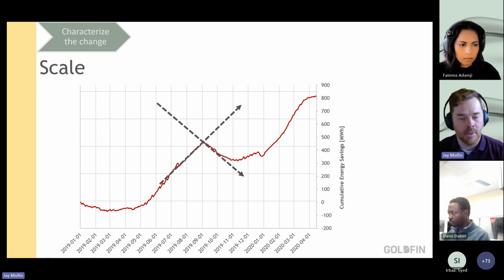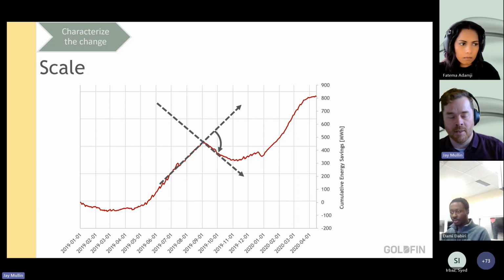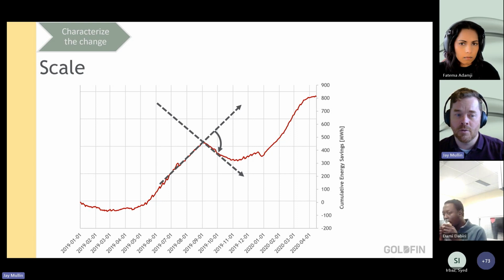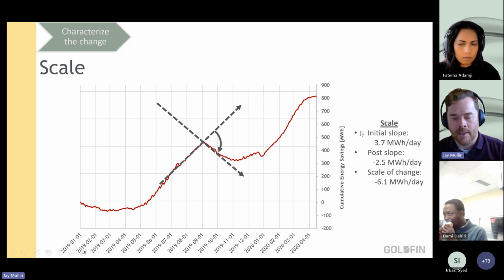The next thing that we can do is look at the scale of the change. Not just what the impact was, but the scale - how much of a change in slope occurred? Now, this one does take a little bit of math that is often outside of programs like RetScreen, but we use just the old slope equals rise over run formula. We can see that before the change, the slope showed we were saving about 3.7 megawatt hours a day.